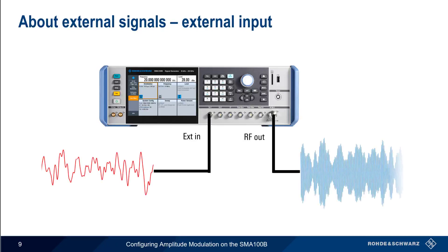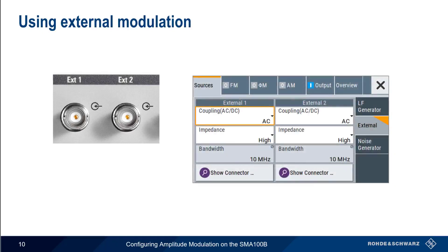In addition to using the internal LF generator, the SMA can also generate signals using an external modulation source to create the modulated RF output. In this case, the input or modulating waveform does not need to be regular or periodic. The SMA100B supports external modulation sources by means of two connectors, External 1 and External 2. Either or both of these BNC connectors can be connected to an external modulation source. For each external connector, we can specify the coupling — AC or DC — as well as the impedance.